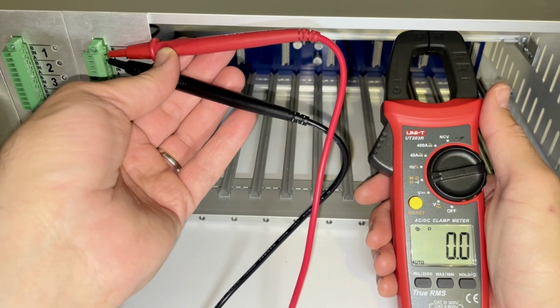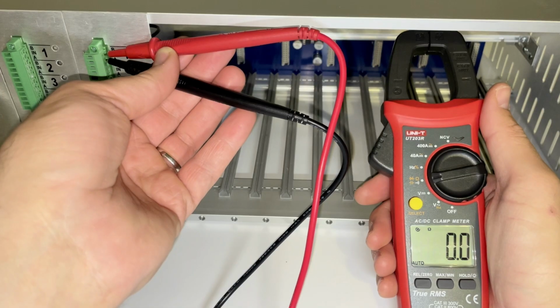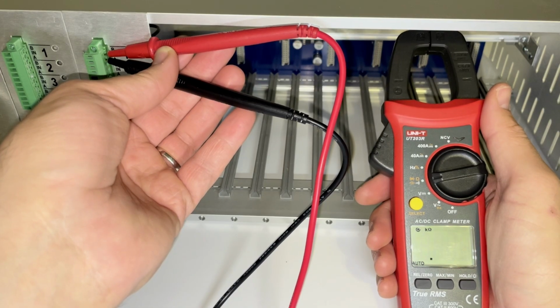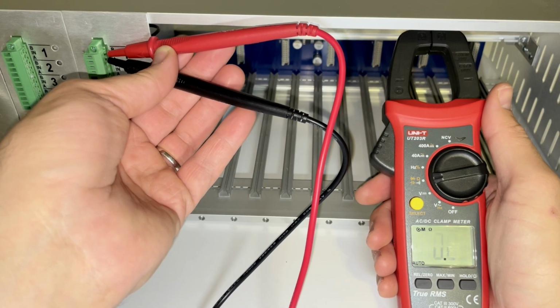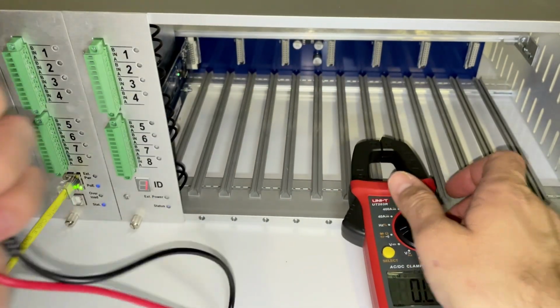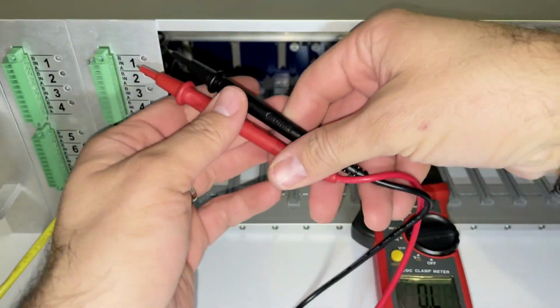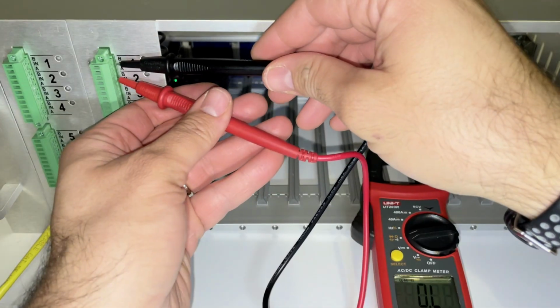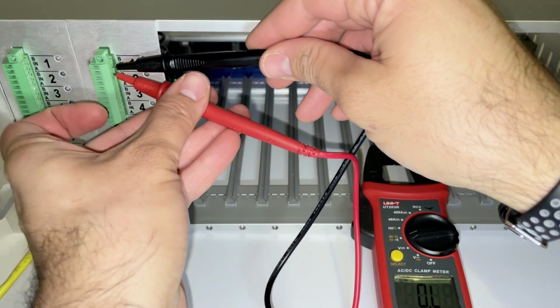Once the system is triggered, the resistance value on the multimeter should drop to approximately 0 ohms, confirming that the normally open and common contacts have closed and a complete electrical path has been established. Next, test the normally closed contact by placing the probes on the common and normally closed terminals.